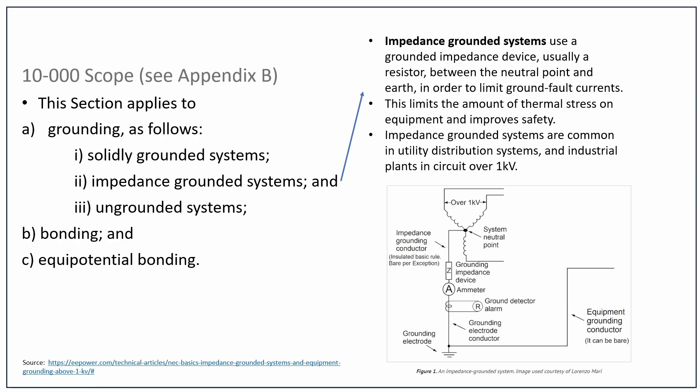There are rules we'll go over for impedance grounded systems — they have to be serviced by qualified individuals, and they also need to have a ground fault detector as well, an alarm that tells you a fault has happened. With solidly grounded systems the neutral was grounded directly without any resistance; with impedance grounded systems, the neutral is grounded but in series before it gets to earth there's either a resistor or some type of coil.